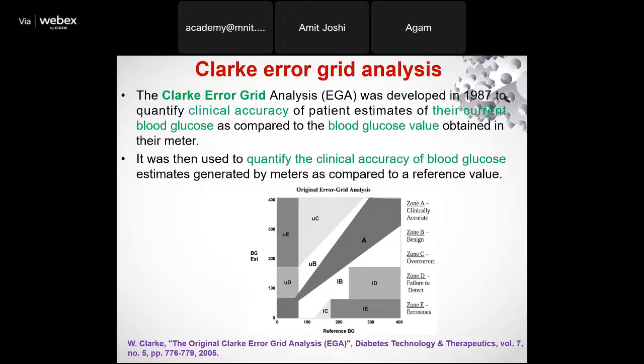Here you observe there is an x-axis and a y-axis. On the x-axis, the reference blood glucose value is measured, and on the y-axis you have the estimated blood glucose value. If your estimated and reference glucose values match, you get a linear relationship, and that relationship resides in zone A. Whenever the reading resides in zone A, we consider that a clinically accurate device.